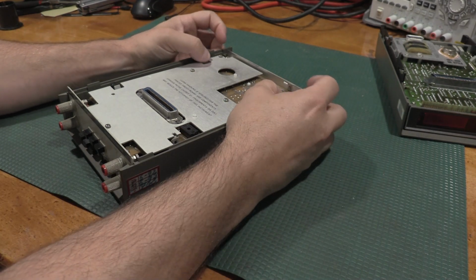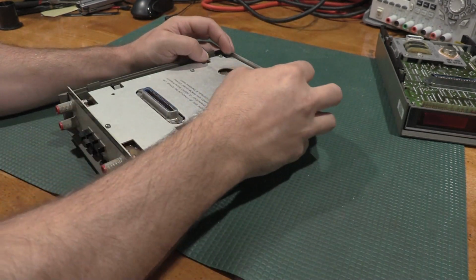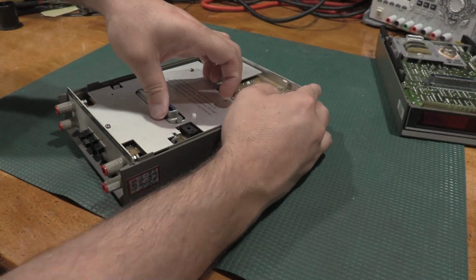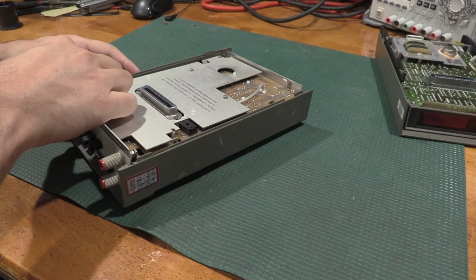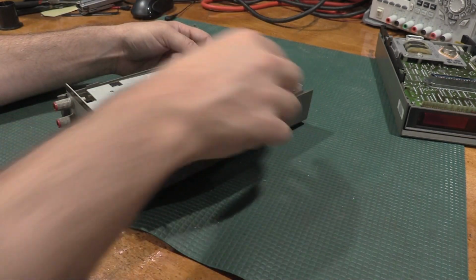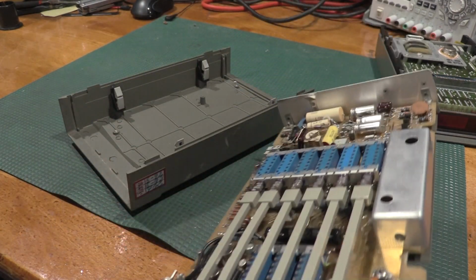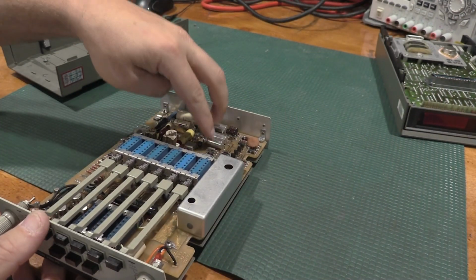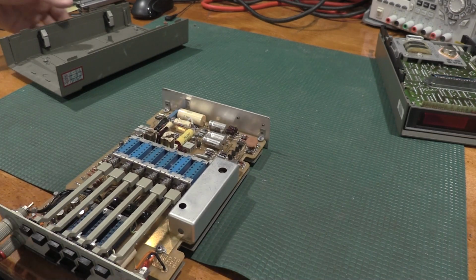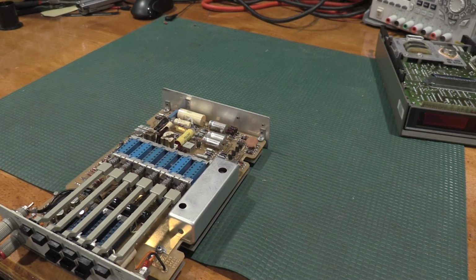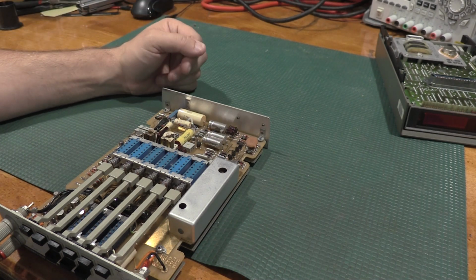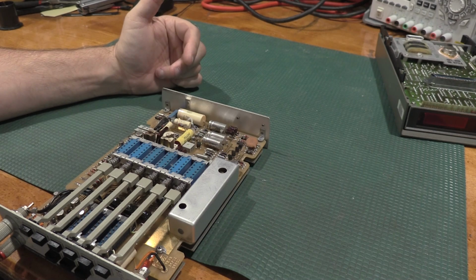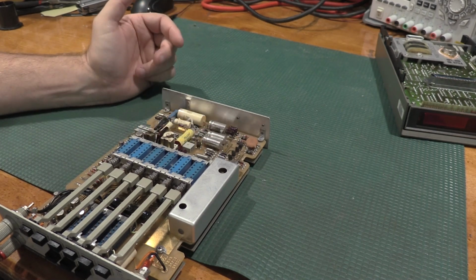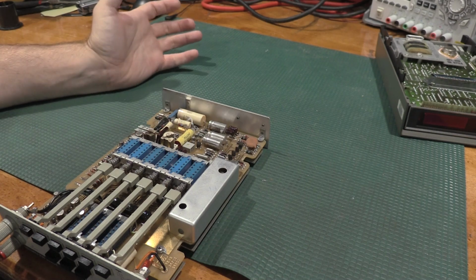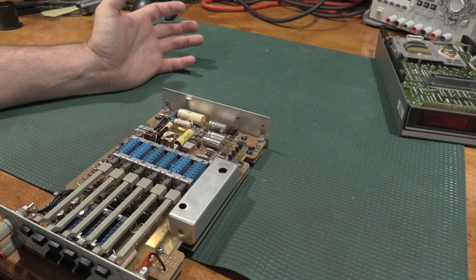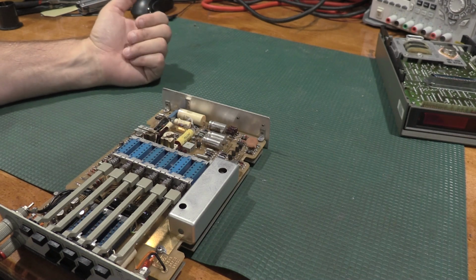This brings us to what we have to do tonight. So what we've got to do tonight is pop this back out, if I can, without too much trouble. What we need to do is these capacitors need to get replaced. They are 100 microfarad, 6.3 volt capacitors, and they are bipolar, which is why I didn't have them in stock in the lab, so I have to get those swapped out. Measuring these from the other unit, because I still have it, they are starting to show some internal leakage, so we're getting high leakage current, which is affecting the meter a bit.